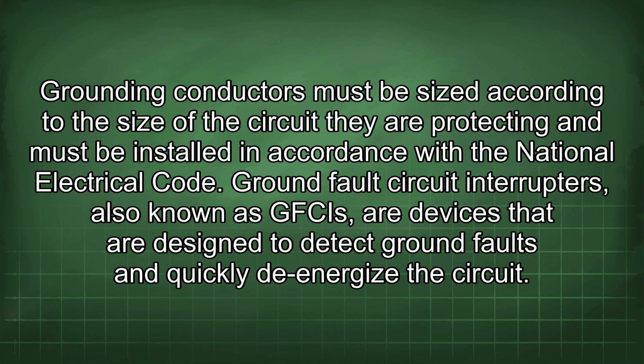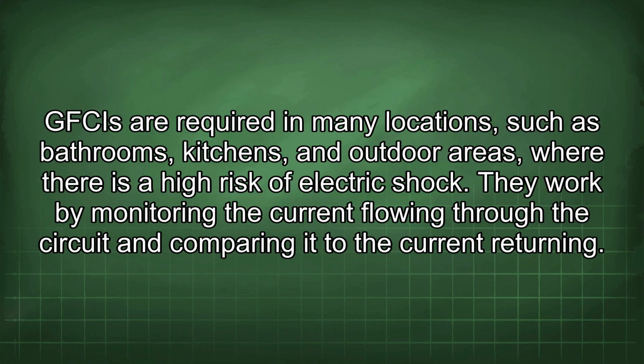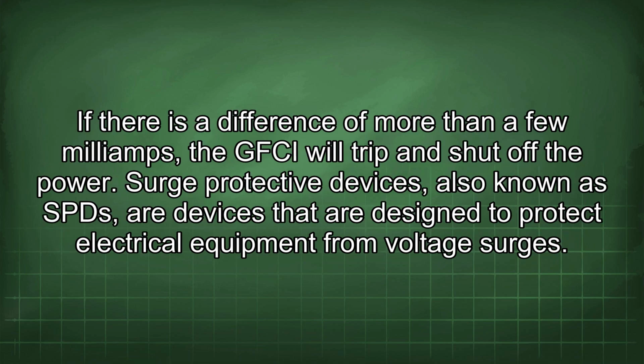Ground fault circuit interrupters, also known as GFCIs, are devices that are designed to detect ground faults and quickly de-energize the circuit. GFCIs are required in many locations, such as bathrooms, kitchens, and outdoor areas where there is a high risk of electric shock. They work by monitoring the current flowing through the circuit and comparing it to the current returning. If there is a difference of more than a few milliamps, the GFCI will trip and shut off the power.